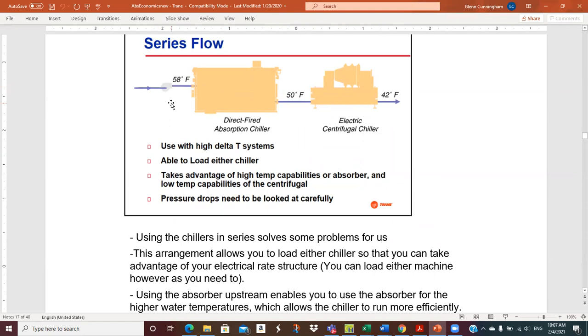Now, that really brings up several interesting issues. More recent design concepts are starting to favor higher delta T systems because the higher the delta T, the lower the flow rate and the smaller the pumps, the distribution energy, and the amount of fluid that you have to flow in order to distribute this cooling capacity to your building. If you've got a 10-degree delta T, you're going to have more water than if you got a 16-degree delta T. Now, older chillers didn't necessarily like some of these different flow rates, but they're becoming much more flexible. So the very newest designs sometimes will reduce condenser water flows below what they traditionally have been, and we'll talk more about that, especially when we get to cooling towers, and also increase the delta T on the chill water side so we can reduce the flow rate. So kind of interesting.